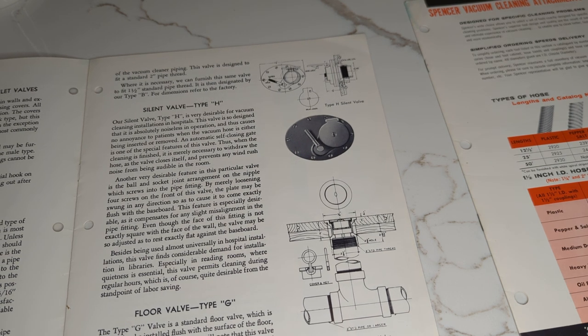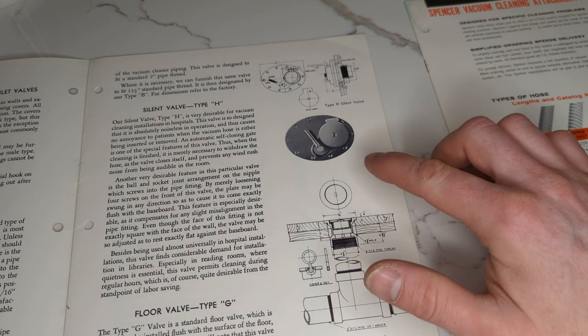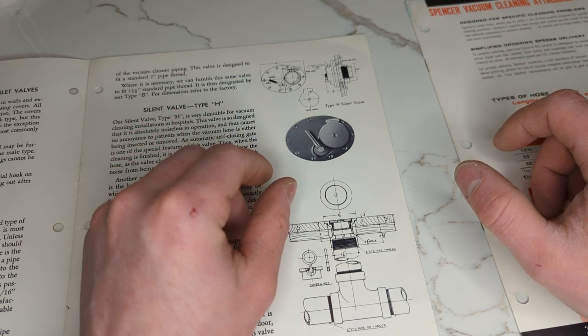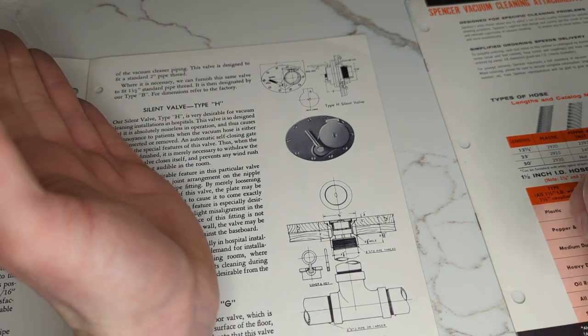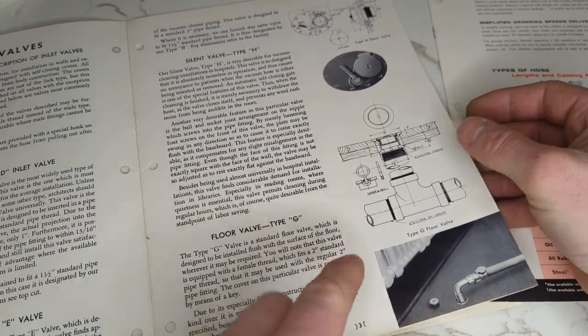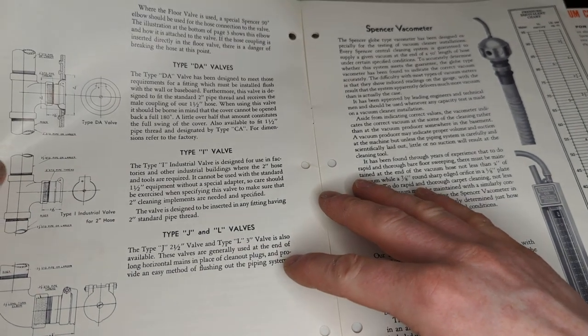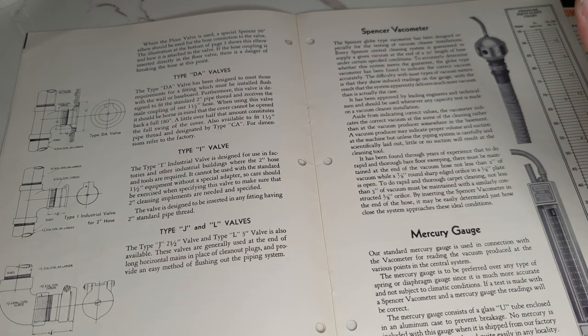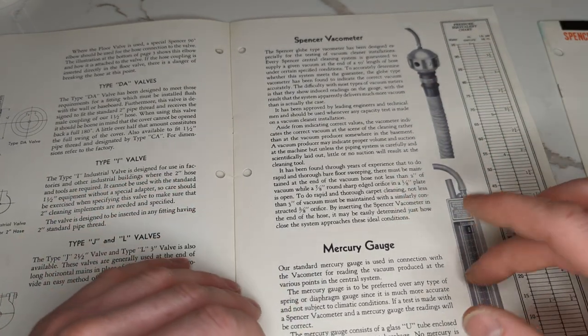The idea was: when you have a system running and you open the valve, it's a loud blast of air. So in an area where that's objectionable, you open the flap, plug the hose in partway, and open the little lever, then plug the hose in fully so the airflow isn't there until after you've plugged the hose in. When withdrawing the hose, that spring-loaded lever closes off before you withdraw the hose completely. That's the silent valve. We have a floor valve with a key that's like a Tueck inlet — but this is obviously post-Tueck. Type DA valve — having it flush is considered a little fancier. And there are inlets for larger size hoses. The Vacometer is now being shown with a mercury gauge instead of a dial gauge.